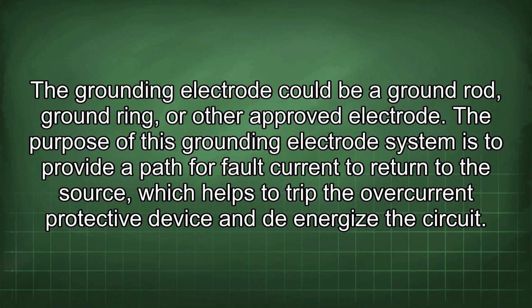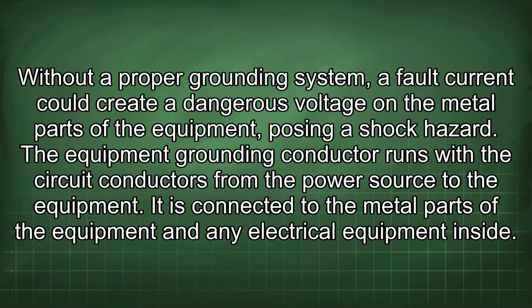The purpose of this grounding electrode system is to provide a path for fault current to return to the source, which helps to trip the overcurrent protective device and to de-energize the circuit. Without a proper grounding system, a fault current could create a dangerous voltage on the metal parts of the equipment, posing a shock hazard. The equipment grounding conductor runs with the circuit conductors from the power source to the equipment.